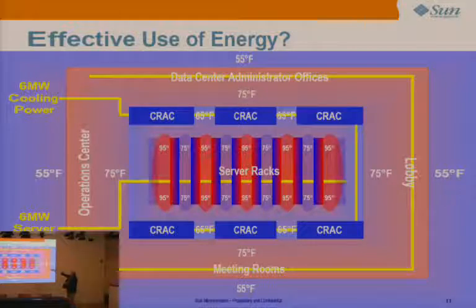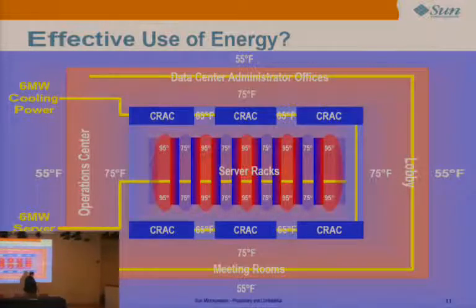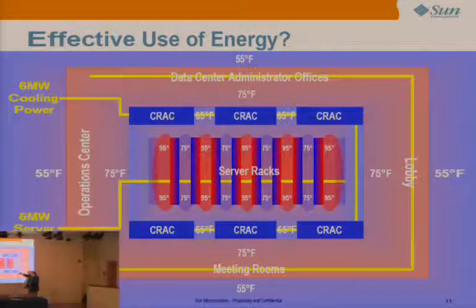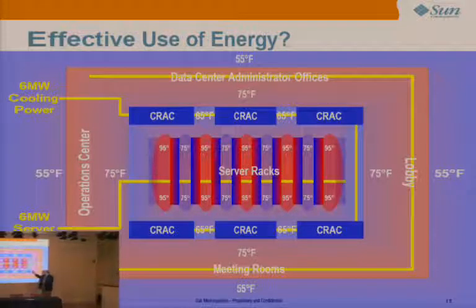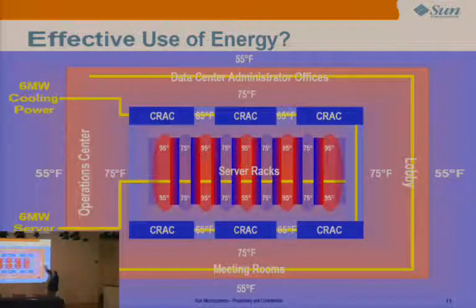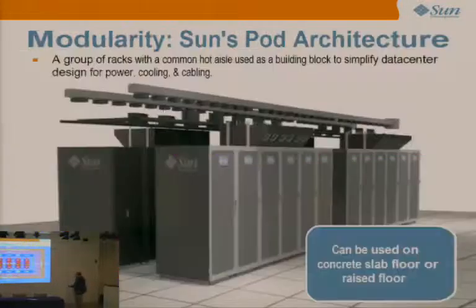So it's not unusual to expect 6 megawatts of cooling power going to the air conditioning units. And because the air conditioning is located right at the edges of the computer room, it makes these offices really, really cold, and so you need heating again. You need 1 megawatt of building heat coming into this office. By the way, this is a generalization of a real example that we studied. The outside air temperature is 55. If you found a way to get that 55-degree air directly to the servers where the cooling is needed, then you'd save a lot of energy.